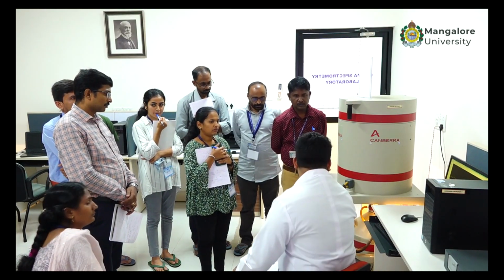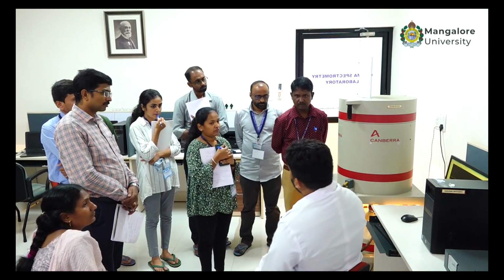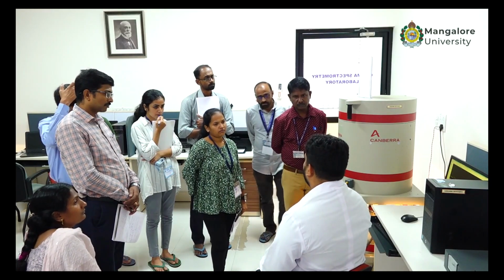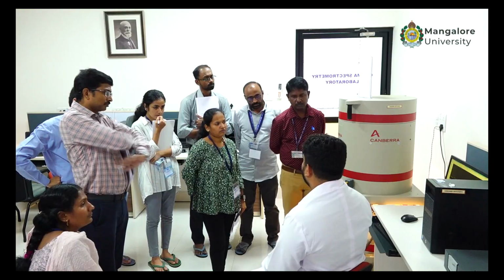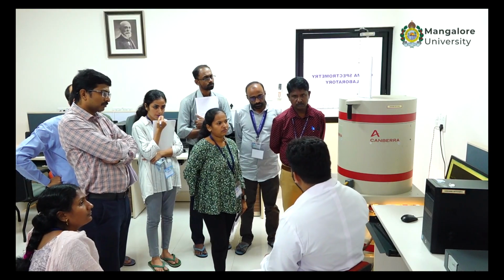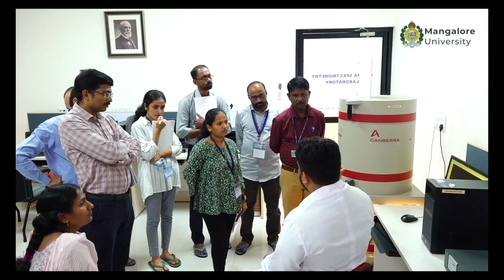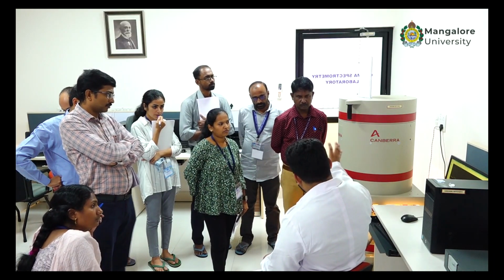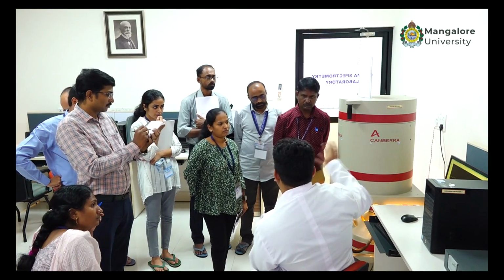Some are P-type, some are N-type. That is a choice depending on how you want it. It does not make very much difference. When you are buying a detector, we mainly look at the nominal efficiency, how efficient it is. A 100% efficient detector means it gives 100% of what sodium iodide gives.